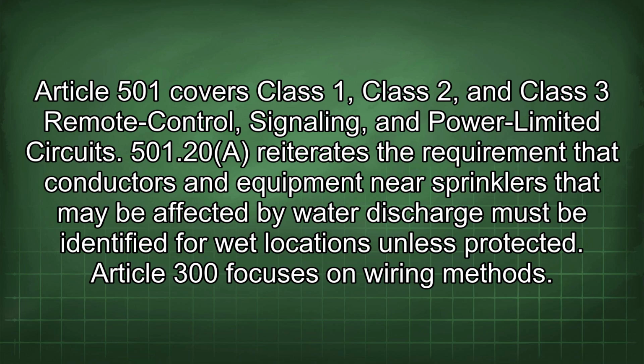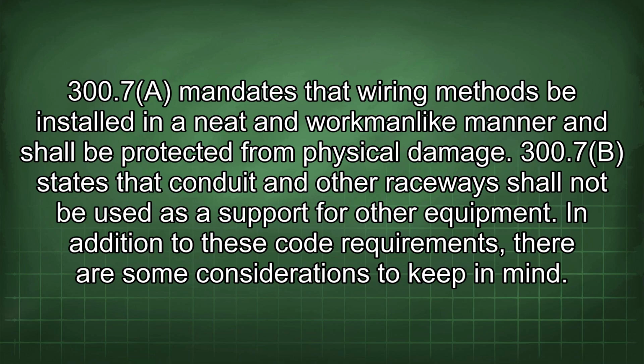Article 300 focuses on wiring methods. 300.7 mandates that wiring methods be installed in a neat and workmanlike manner and shall be protected from physical damage. 300.7(B) states that conduit and other raceways shall not be used as a support for other equipment.